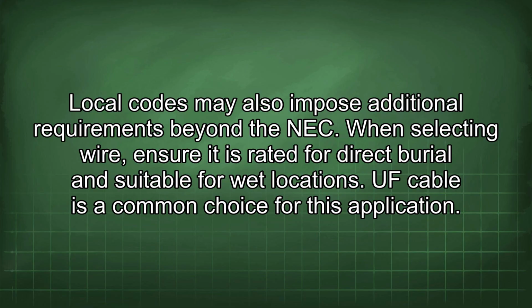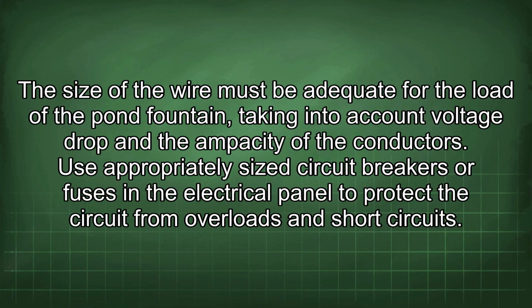When selecting wire, ensure it is rated for direct burial and suitable for wet locations. UF cable is a common choice for this application. The size of the wire must be adequate for the load of the pond fountain, taking into account voltage drop and the ampacity of the conductors. Use appropriately sized circuit breakers or fuses in the electrical panel to protect the circuit from overloads and short circuits.